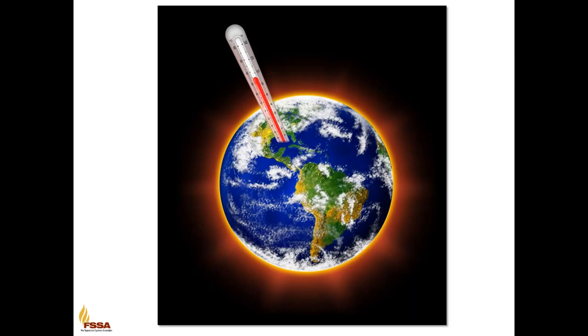As discussed in the opening session, the EPA SNAP approved halocarbon and inert gas clean agents have zero ozone depletion potential, or a zero ODP. These new agents are not without their own environmental issues, however, as the concern for global warming potential has become more of a factor. The global warming potential, or GWP, of a given gas is determined primarily by its ability to trap heat and how long the gas will remain in the atmosphere. The GWP compares how much heat a given mass of gas will trap in a given time as compared to the same mass of carbon dioxide. Carbon dioxide is given a GWP value of 1. So an agent with a GWP of 100 has the same warming effect for each pound as that of 100 pounds of CO2.